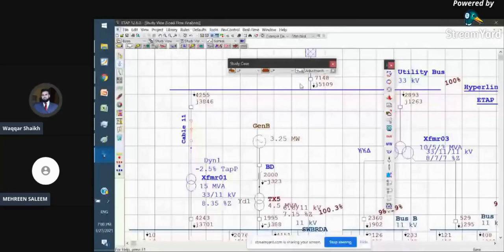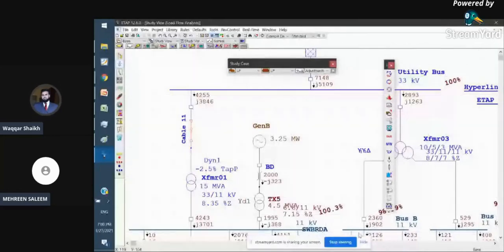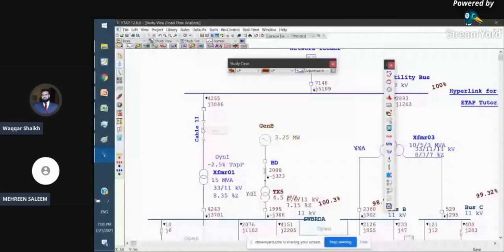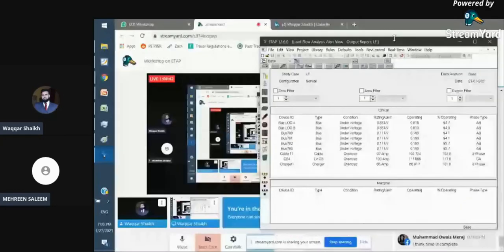When I run the simulation, I find that cable 11's color has changed. If I go into the alert view, it will indicate the problem. For example, cable 11 has an overload problem. You can see this cable is rated for 97 amps, but it is operating at 103 amps.